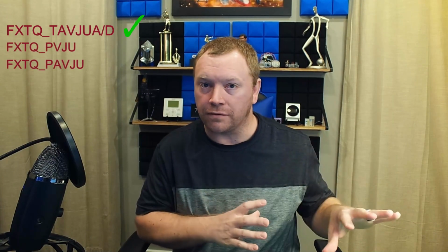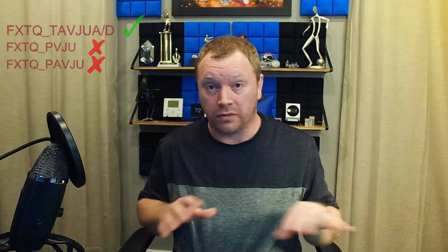Now, as far as the FXTQ air handler goes, the only note disclaimer that I will put in for this video is we are only talking about today's air handler. It's the FXTQ that ends with the suffix in the model number TAVJU and an A or a D at the end. Either it does or does not come with a built-in circuit breaker is the only difference, but we're not talking about the older FXTQ PVJUs. They have a totally different strip heat, part number, different connection, different board, different settings entirely. They do not cross over at all.